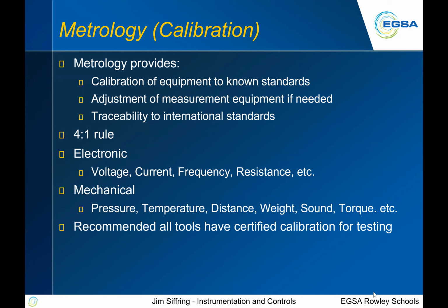So metrology provides calibration of equipment to a known standard. If you need to adjust that tool, we can adjust it, and it provides traceability to those standards. There's a rule in metrology, the 4-to-1 rule, that basically means if you're going to test a voltmeter on a genset, and that voltmeter on the front panel of your genset is good to say plus or minus 2% accuracy, the device you test it with has to be 4 times better than that, or plus or minus 1/2 of 1%. So that's what the 4-to-1 rule is. If you have a 4% meter, you need to calibrate with a plus or minus 1% meter.